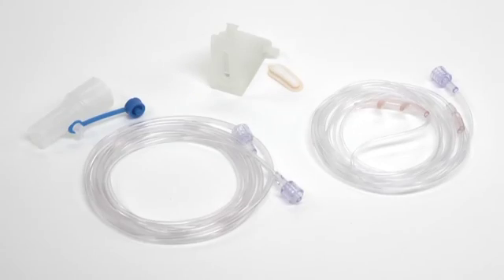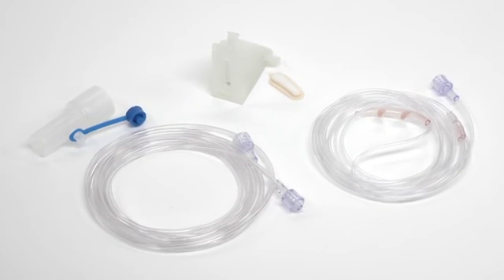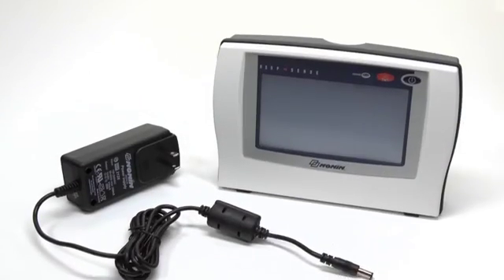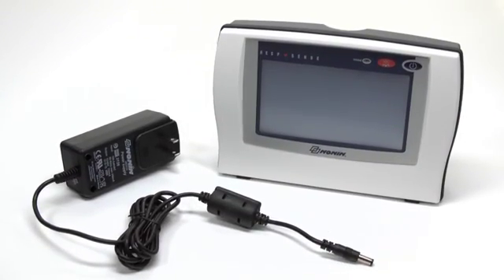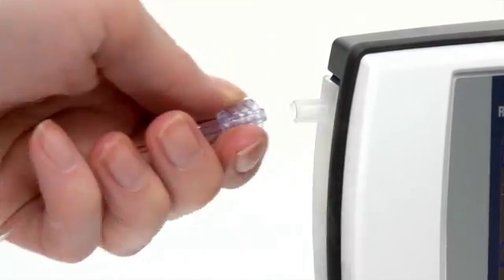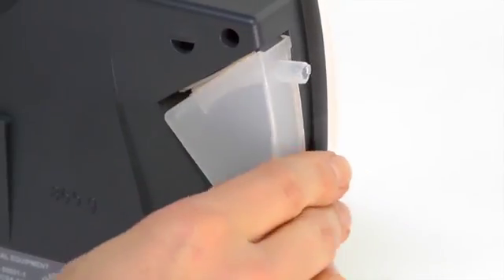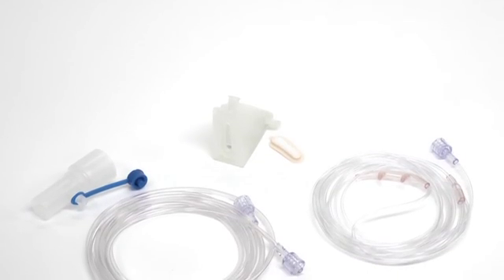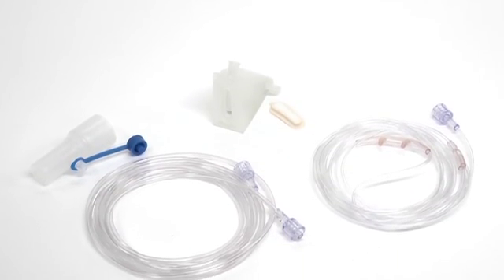Setup consists of a monitor, moisture trap with filter, nasal cannula or T-connector and sample line, and the power supply. Moisture traps, filters, and sample lines are single-use components and are disposed of after each patient use. Start each patient with a new sample line, moisture trap, and filter.